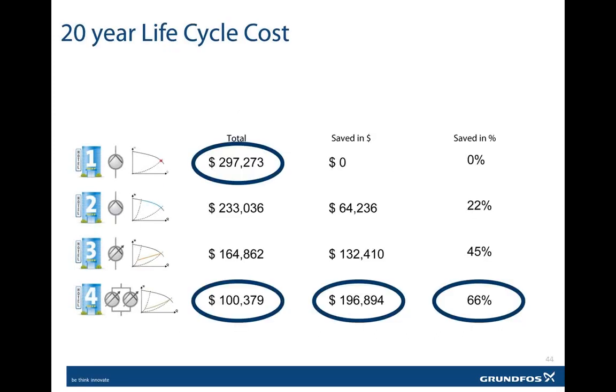So now if we look at the difference between the single constant speed, constant volume pump versus the parallel variable speed, variable volume Magna 3, we can see that there's 1/3 of the operating cost over the life cycle of the pump. This is where we see really the true life cycle cost analysis difference. So we can see over a 66% energy savings in the cost of the system.